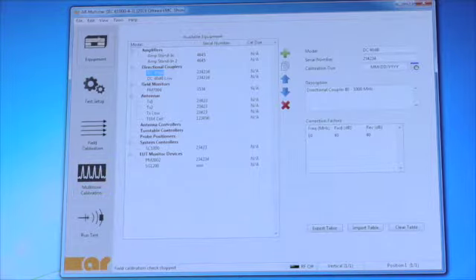So the first thing I tell everybody is to load all your test lab equipment in the equipment list here. Here you can see we have a directional coupler, and you put all your information here: your model number, your serial number, calibration due date, description, and then your correction factors. So any other piece of equipment that needs correction factors, here's where you would insert all that. And you can import it from a table file or a text file. Now, after you have all your equipment loaded in, you're ready to do the test setup.